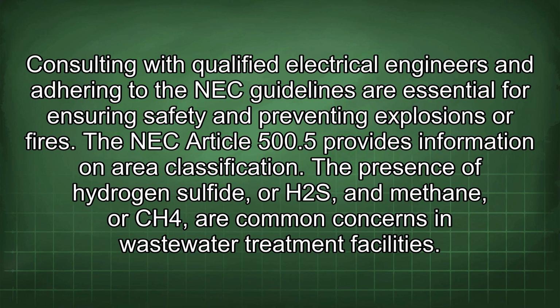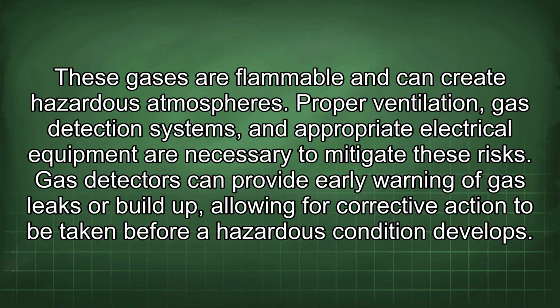Consulting with qualified electrical engineers and adhering to the NEC guidelines are essential for ensuring safety and preventing explosions or fires. The NEC Article 500.5 provides information on area classification. The presence of hydrogen sulfide, or H2S, and methane, or CH4, are common concerns in wastewater treatment facilities. These gases are flammable and can create hazardous atmospheres. Proper ventilation, gas detection systems, and appropriate electrical equipment are necessary to mitigate these risks.